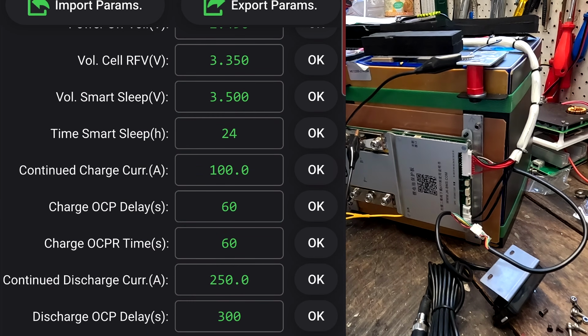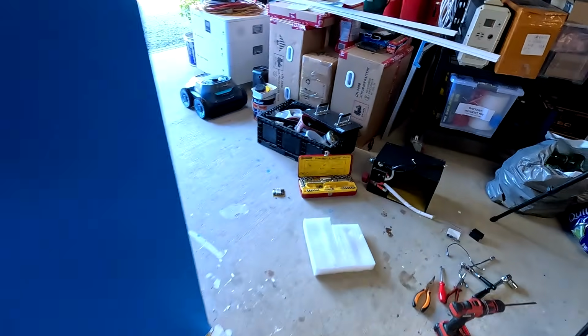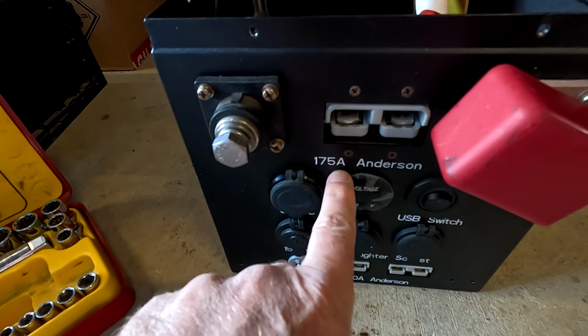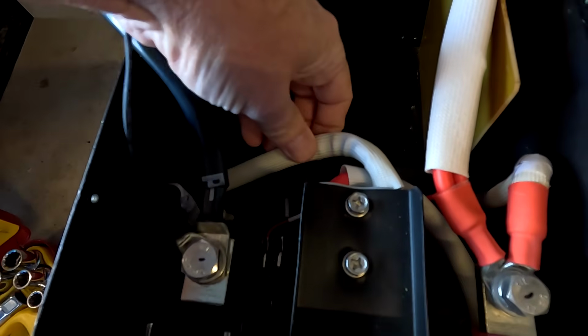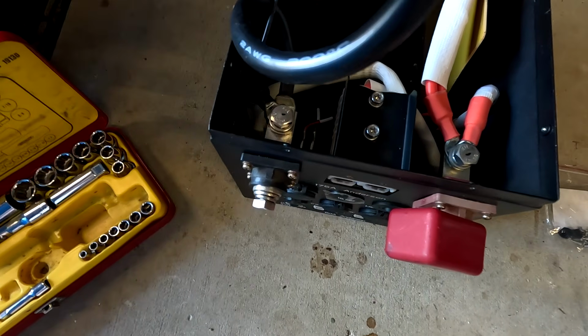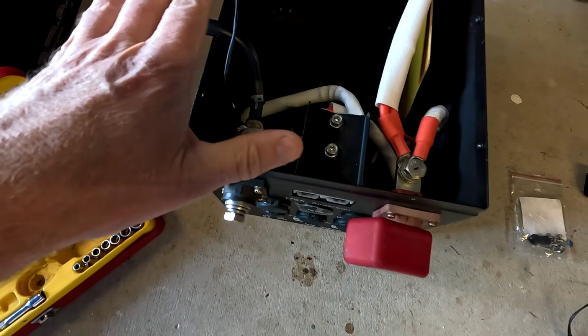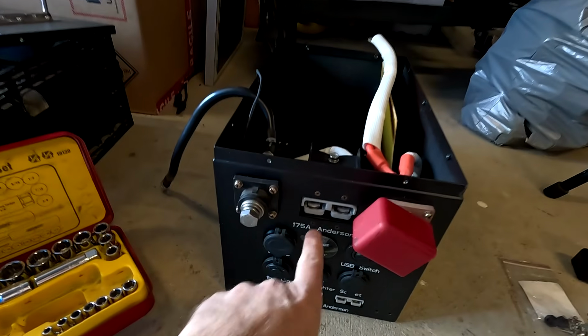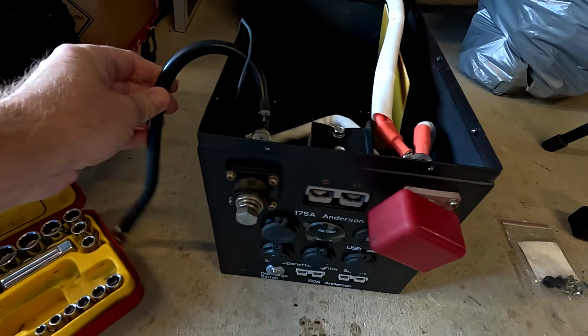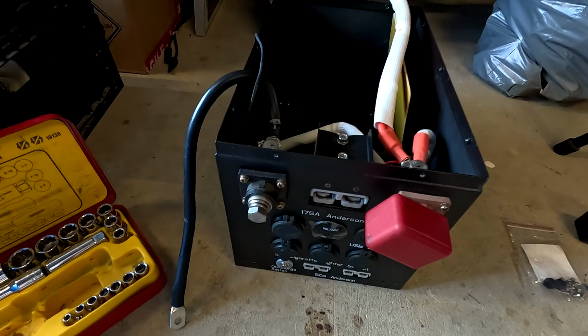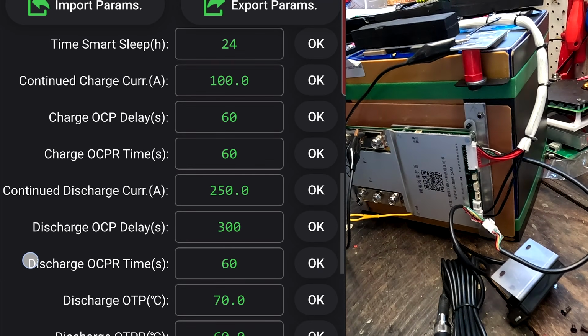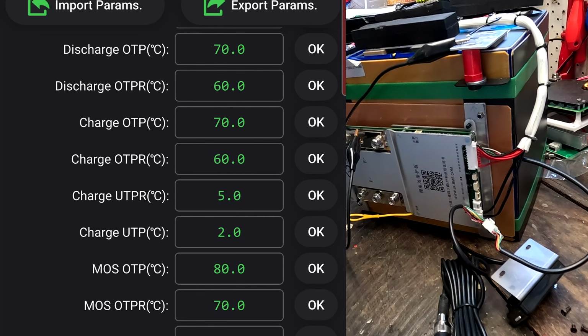I'm not sure 250 amps is actually a lot for these cables inside this box. This Anderson connector here at the front, when you have a look again, there is a 175 amp Anderson connector, but the cabling is only like 16 mil or something. I mean, even the main cable to the battery is only a 2-gauge wire, which is not even 50 square mil. Ooh, I know the silicon cable, it can carry a bit more, but it will get hot as well, and you don't want any heat inside this box either, right? So 175 amps, I would have gone with a 70 mil cable with a 1-gauge wire. But hey, it is what it is now. Yeah, we set this to 250. Okay. Temperatures, yeah, we need to see what the temperatures are doing inside this box then.